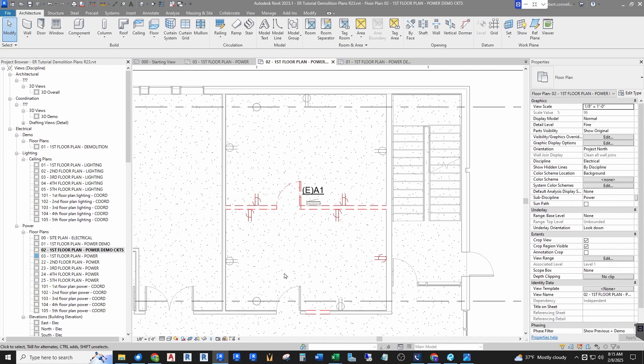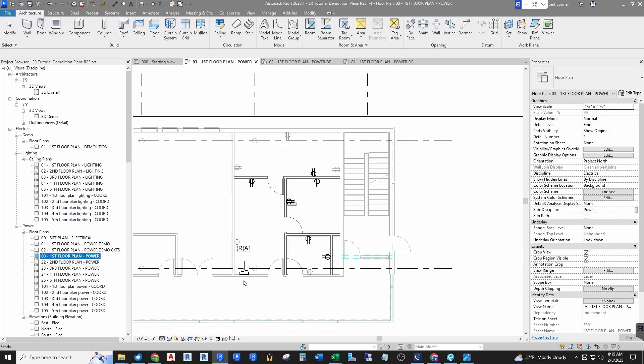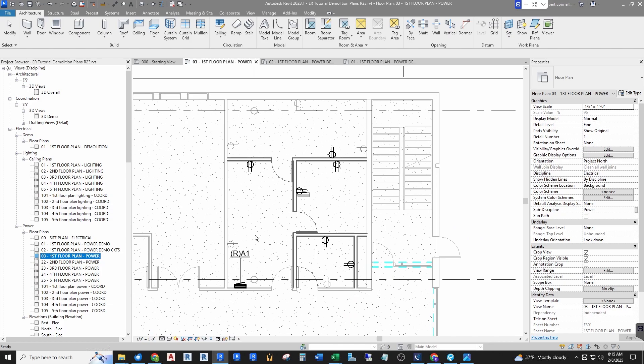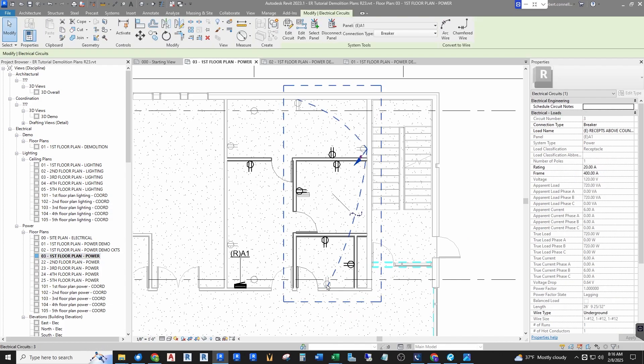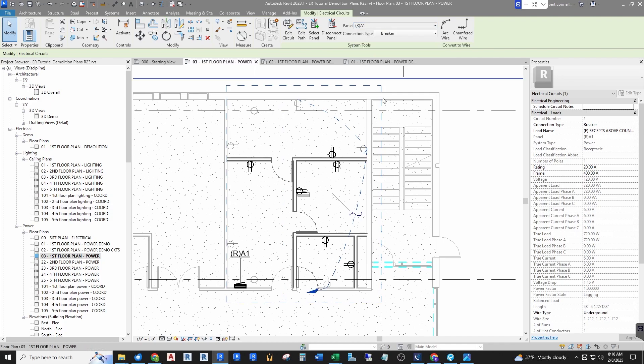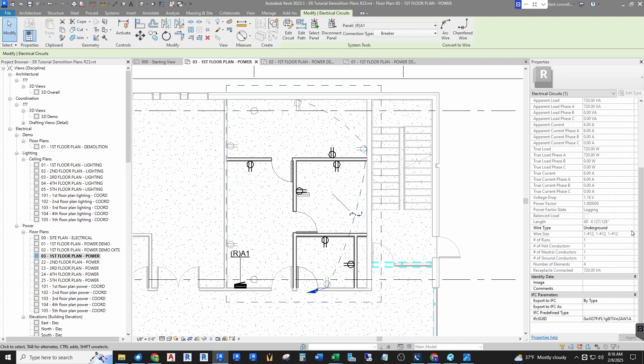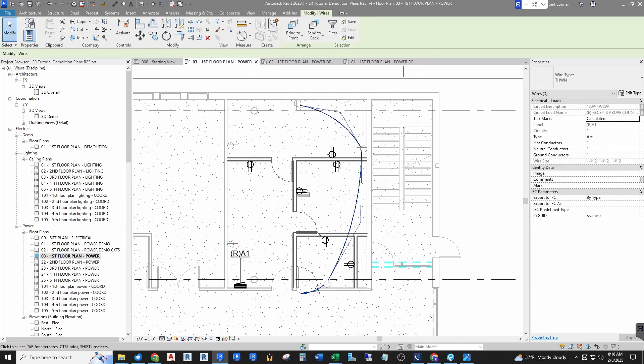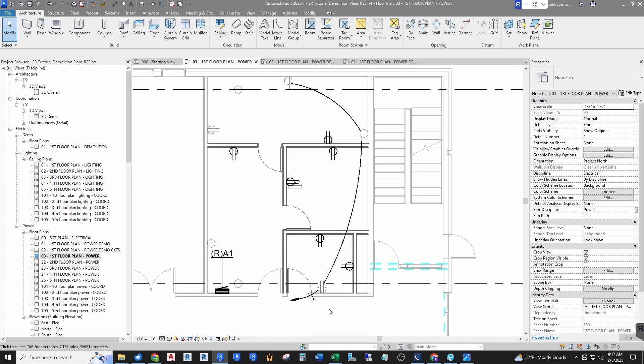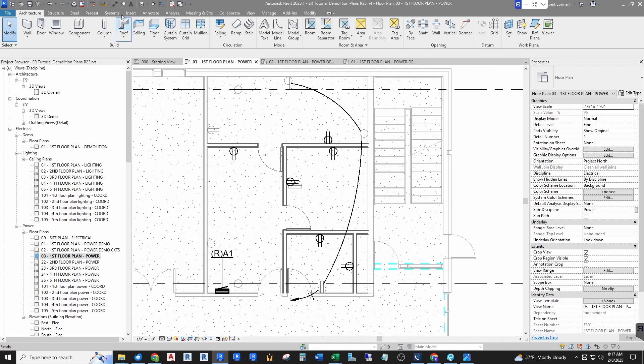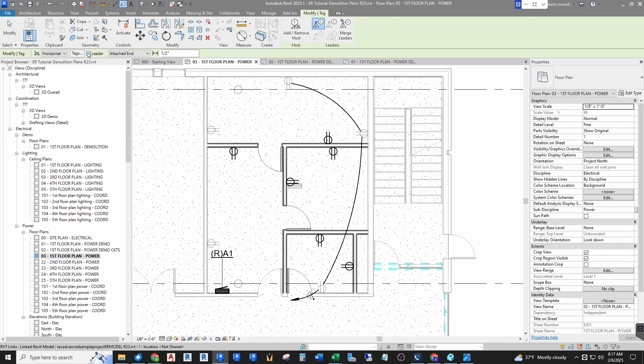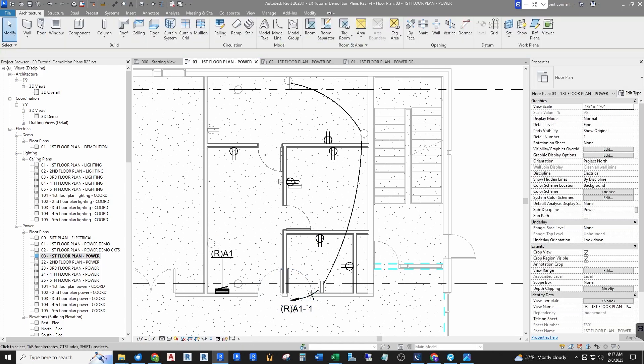There. So now I have a clean demo plan without the circuiting showing. In my new power plan I do want things to be circuited, so I'm going to hover over this circuit and I need to change it to the R panel. And I need to make sure that I'm using the right wire type. I had previously shown an underground type of wire, we don't want that. And then hit the arc wire and there we go, it avoids that one receptacle that is demoed. So now I can show this connected without a leader to my relocated panel.